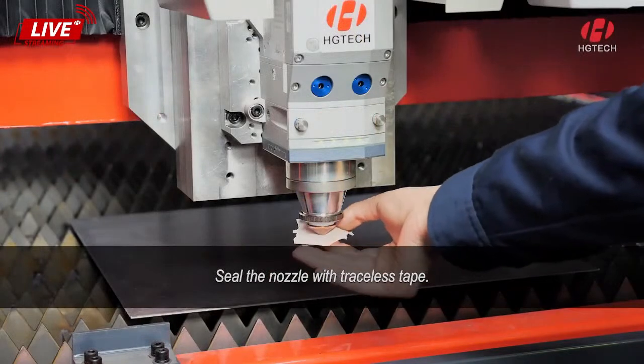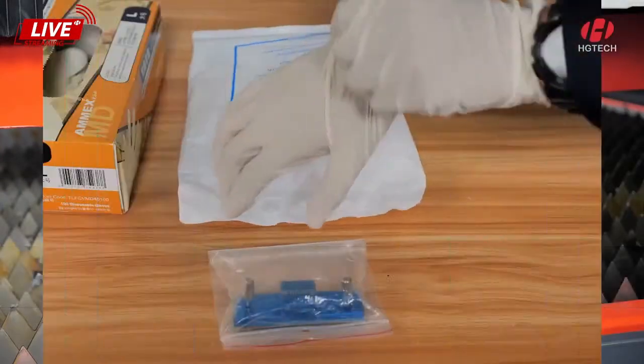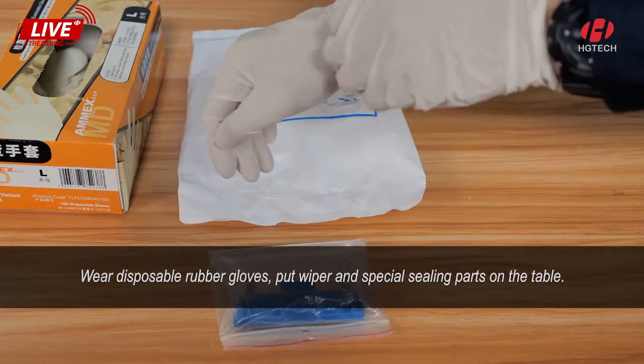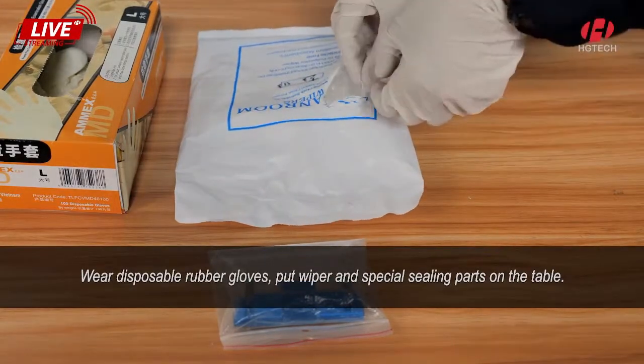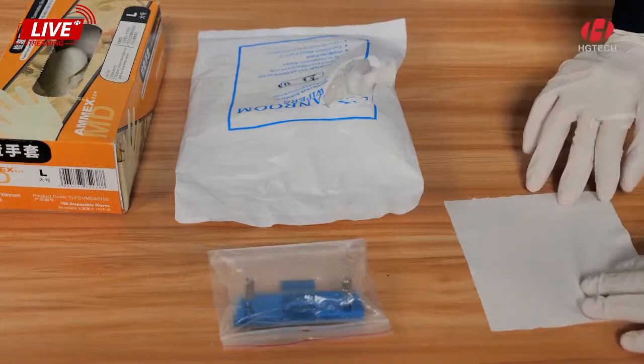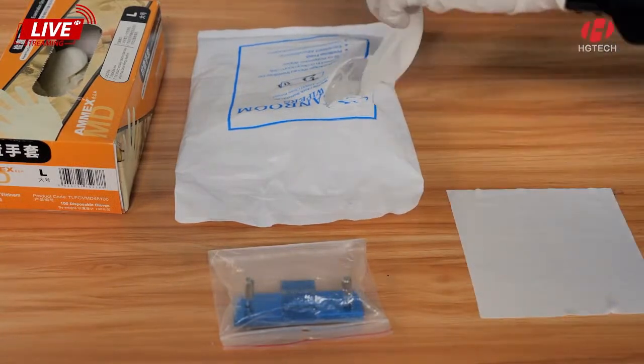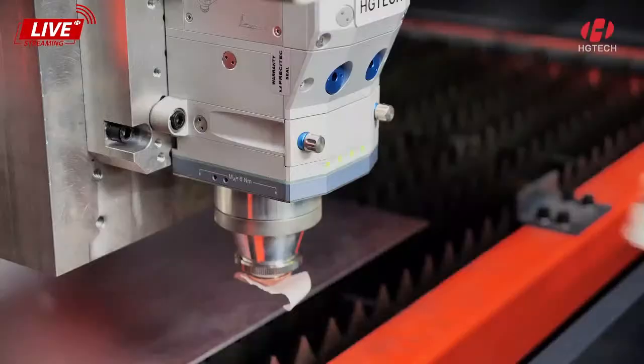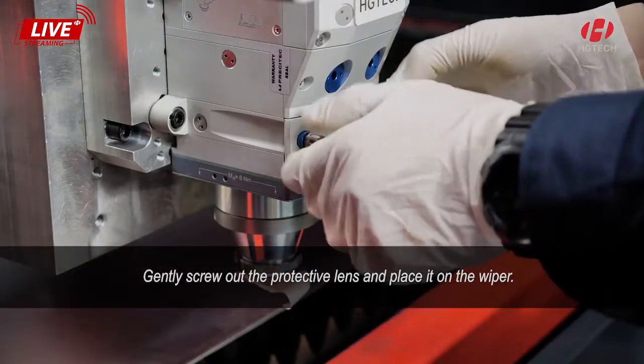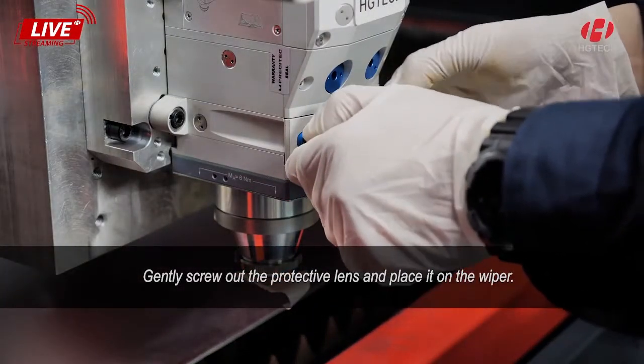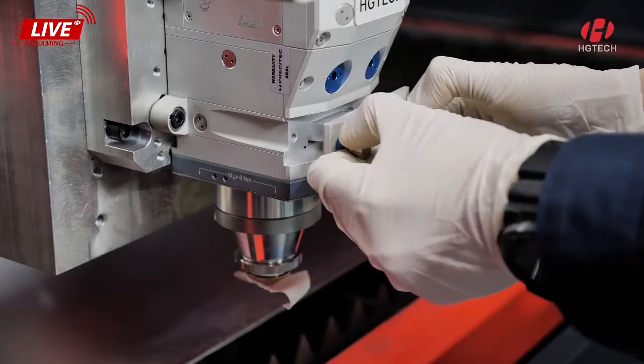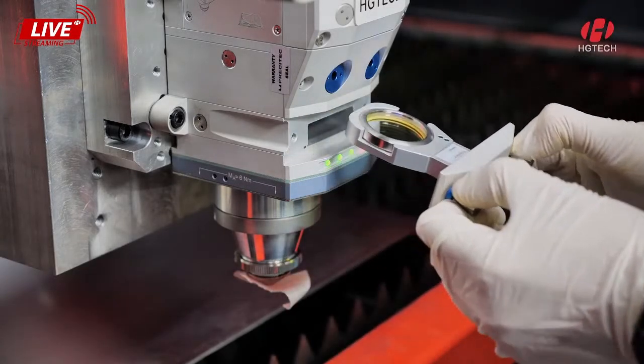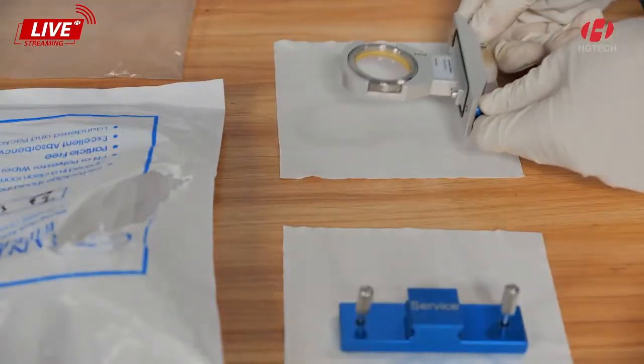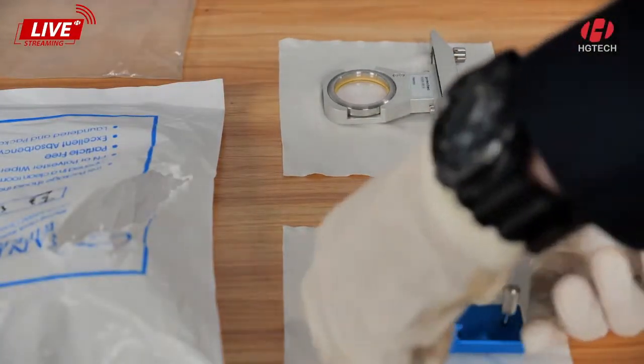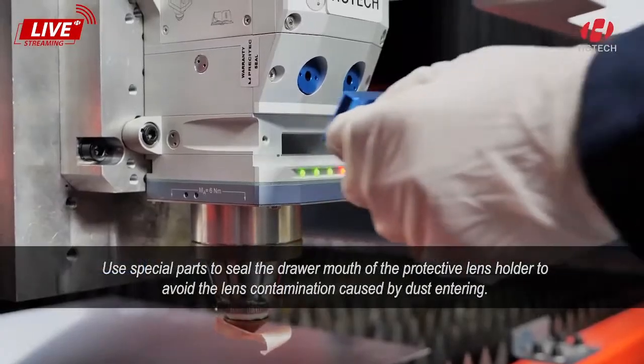Seal the nozzle with traceless tape. Wear disposable rubber gloves, and put the wiper and special sealing parts on the table. Gently slide out the protective lens and place it on the wiper. Use special parts to seal the drawer of the protective lens holder to avoid lens contamination caused by dust entering.